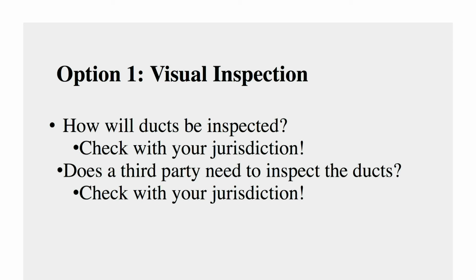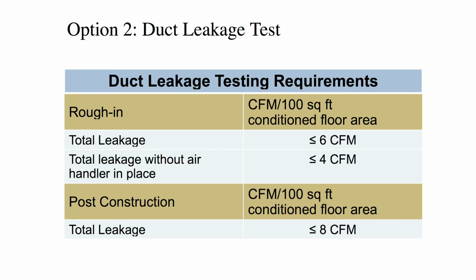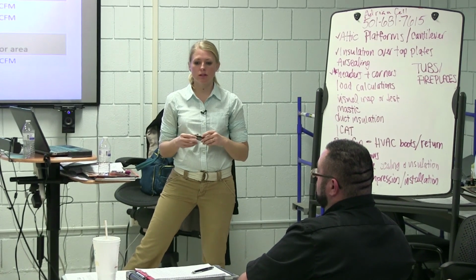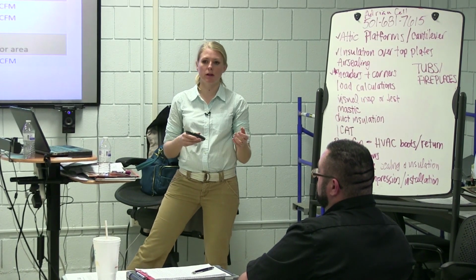So, visual inspection. This is one option to make sure that your ducts are passing code. The code does not state who will do the visual inspection. It just says that there has to be a visual inspection. If you want to do duct leakage testing, there are certain numbers that you have to meet. With the duct leakage testing, the code does not state who has to do it. The only thing that they do state is that the jurisdiction may require a third party if they want to.